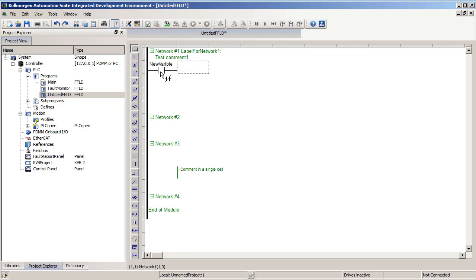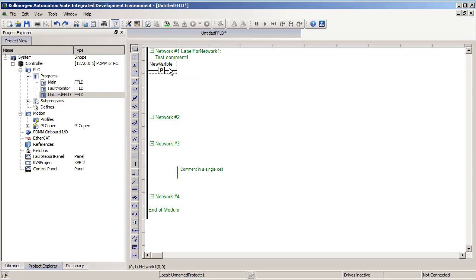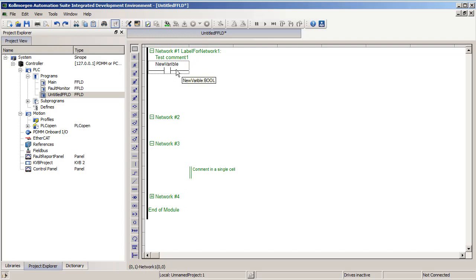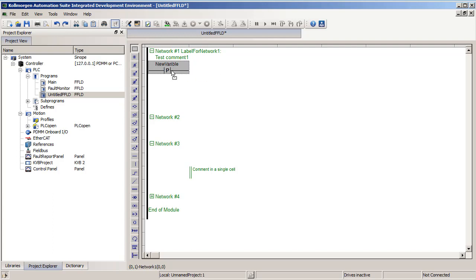I can also click the different types to add the different types of contacts. One shortcut is when a contact or coil is highlighted, you can hit the space bar to cycle through all the different types that we have. The first, or normally open, will allow power to flow through it when the variable assigned to it is true. The second, or normally closed, will be the opposite. It will allow power to flow through while that variable is false.